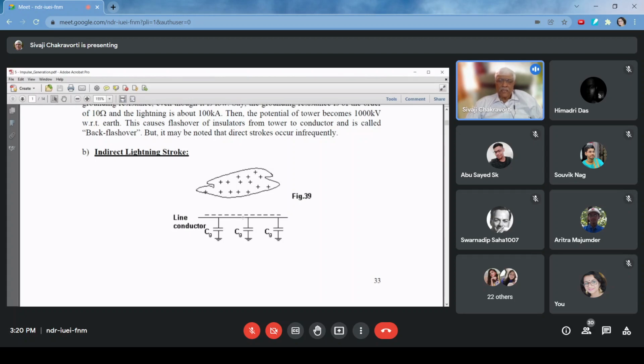Effectively there will be a traveling wave. Again, these are all charges, so the movement of them is effectively a current. So there is a traveling wave phenomenon, and that will give rise to certain overvoltages. These will not be as high as with the direct lightning stroke, but definitely significantly higher than the normal voltage. But as I said, these voltages can happen multiple times in a single day. So primary consideration is always given to protecting our equipment against indirect lightning strokes, that means the voltages generated due to indirect lightning strokes.